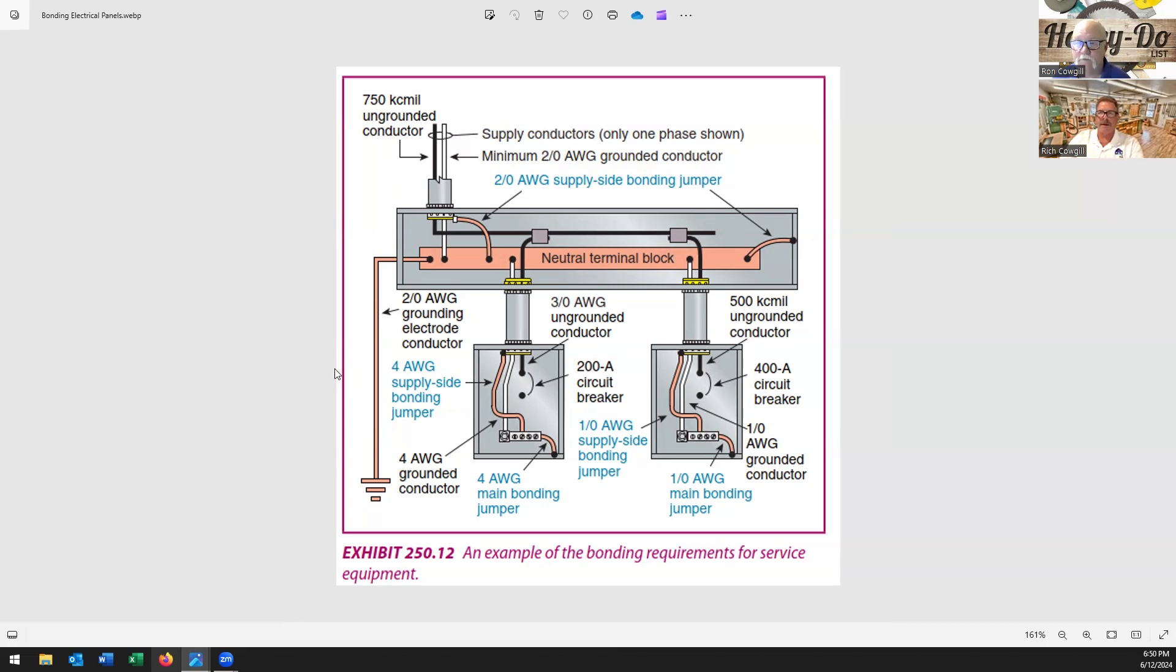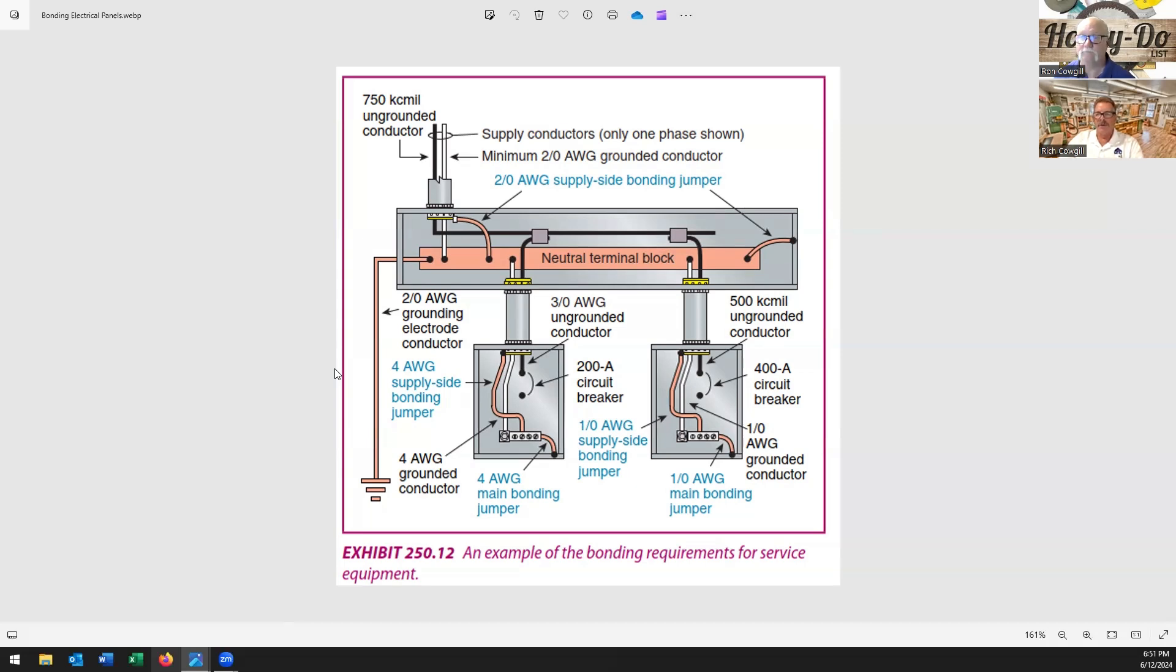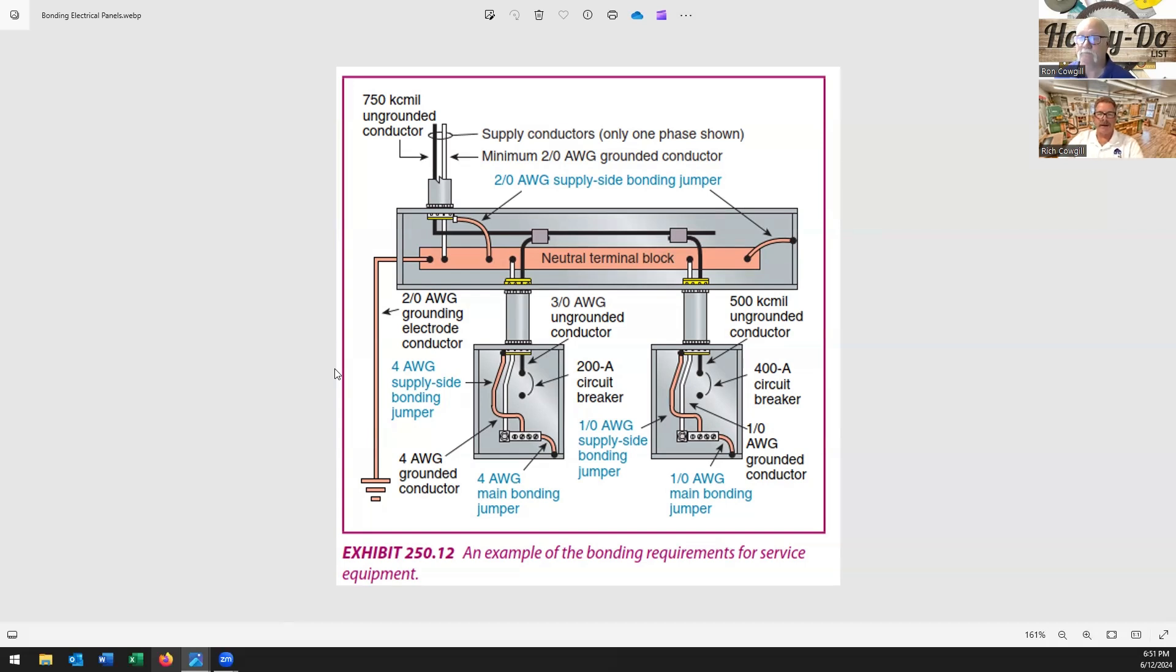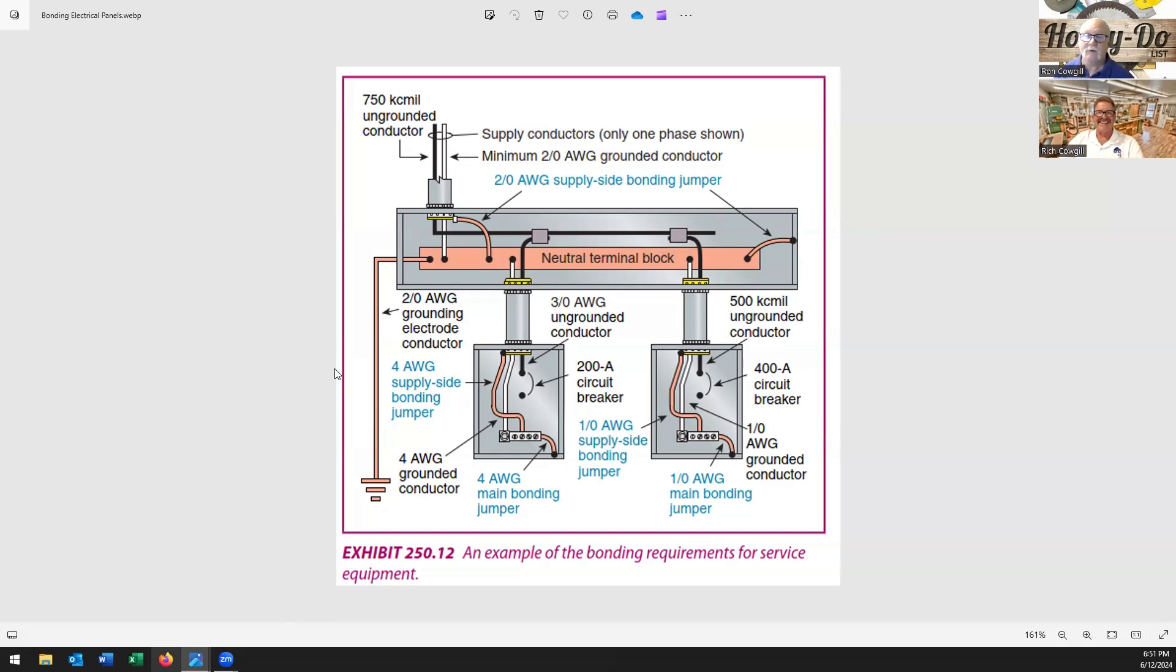If you had a pacemaker and you were holding the shower valve which happens to be brass, and you stepped on the drain or the water line - you know anything connected to the copper - it literally could send milliamps through your body which most people would never notice. But if you had a pacemaker it could stop it. And that's where all this kind of came from and it started making a lot more sense after he told me that. And I also appreciated, you know what I mean, it's like now I get it and never had a problem bonding things since. Yeah, because he took the time to explain it to you.